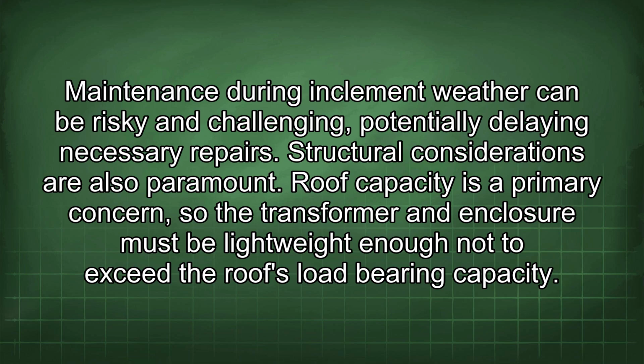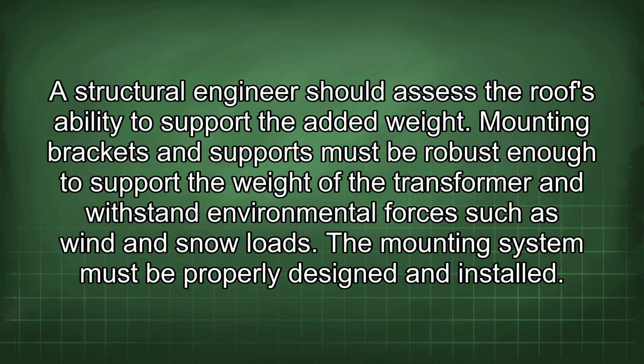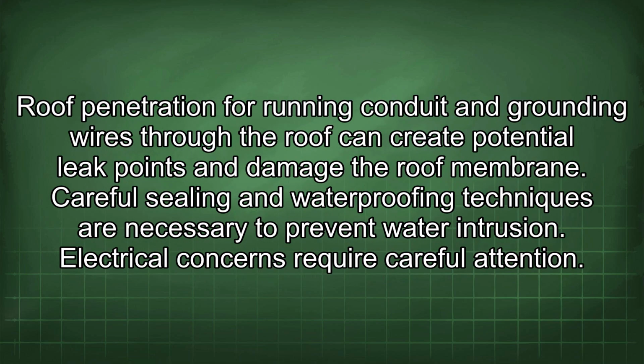Structural considerations are also paramount. Roof capacity is a primary concern, so the transformer and enclosure must be lightweight enough not to exceed the roof's load-bearing capacity. A structural engineer should assess the roof's ability to support the added weight. Mounting brackets and supports must be robust enough to support the weight of the transformer and withstand environmental forces such as wind and snow loads. The mounting system must be properly designed and installed. Roof penetration for running conduit and grounding wires through the roof can create potential leak points and damage the roof membrane. Careful sealing and waterproofing techniques are necessary to prevent water intrusion.